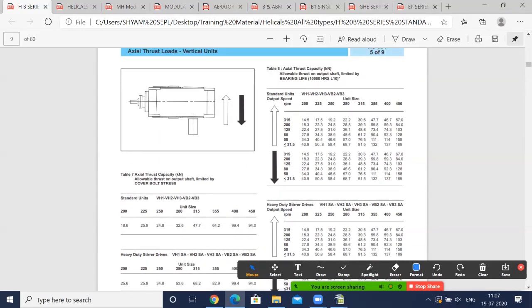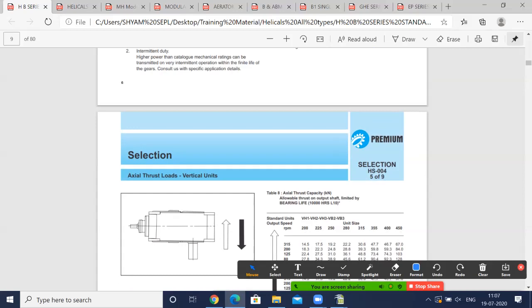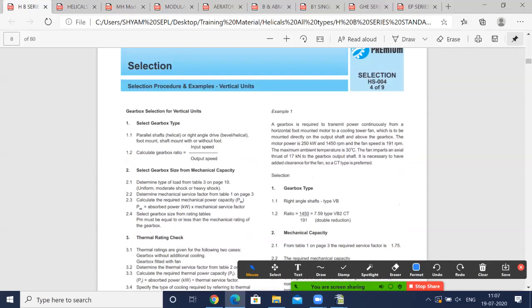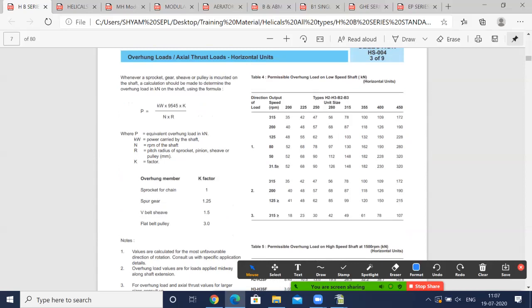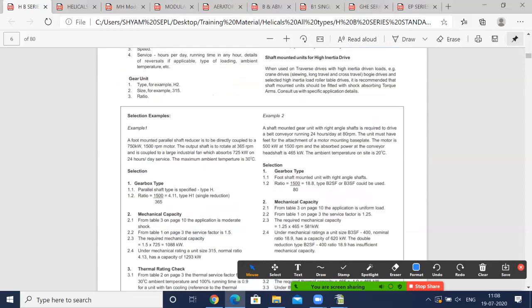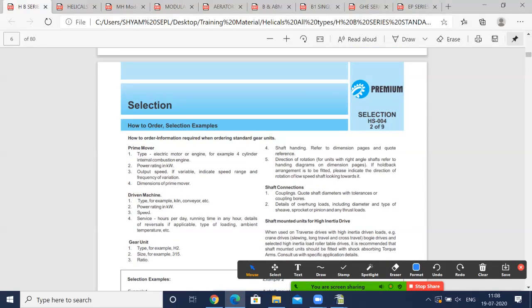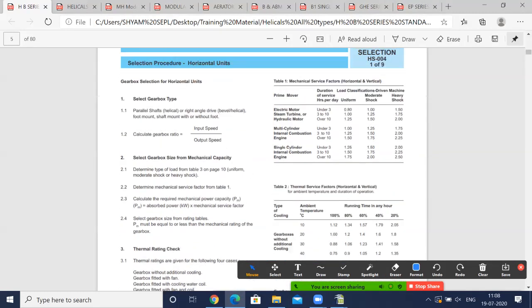If needed on the output side, besides the standard bearing, we can use a thrust bearing housing. We can use an additional bearing housing. So if the thrust of the application is high, you need to see these figures as well. Then other factors given here are like kilowatt to Newton meter. So you can even convert the overhang load into power, and from power you can work out the overhang load. And similarly, you can also convert kilowatt to torque.